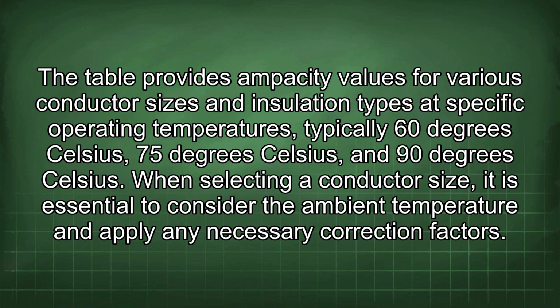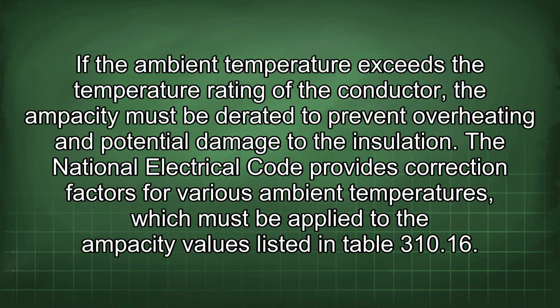When selecting a conductor size, it is essential to consider the ambient temperature and apply any necessary correction factors. If the ambient temperature exceeds the temperature rating of the conductor, the ampacity must be derated to prevent overheating and potential damage to the insulation. The National Electrical Code provides correction factors for various ambient temperatures, which must be applied to the ampacity values listed in Table 310.16.